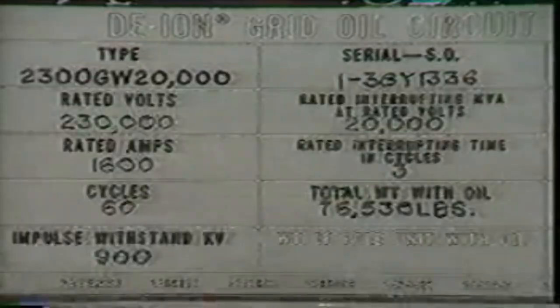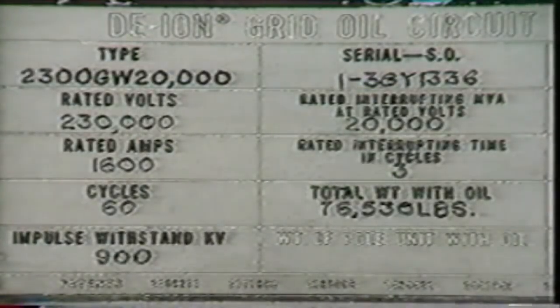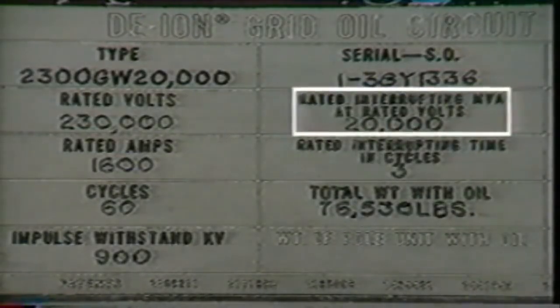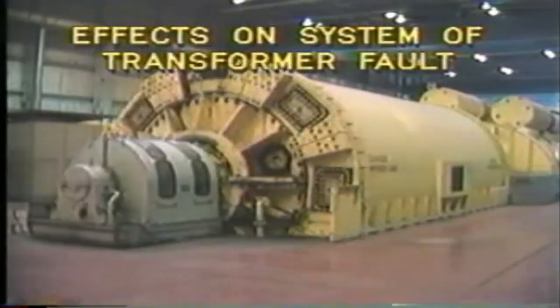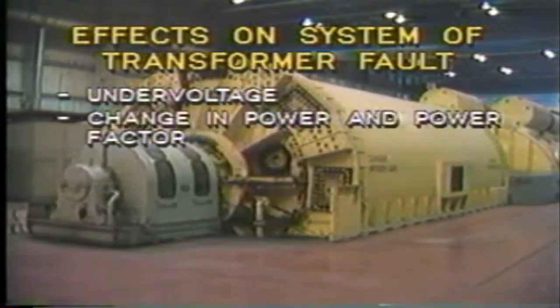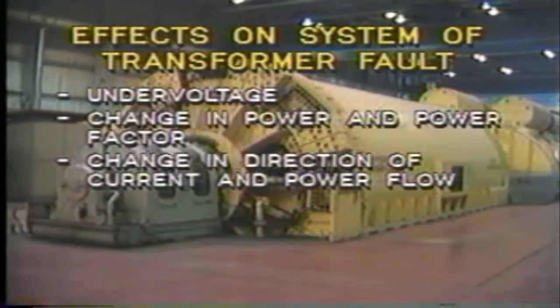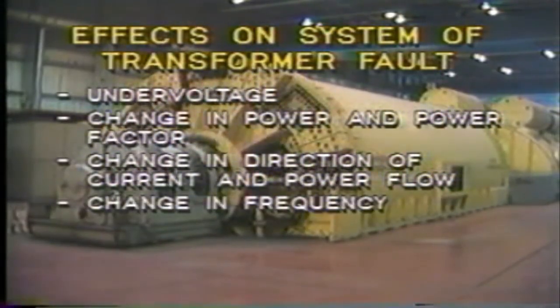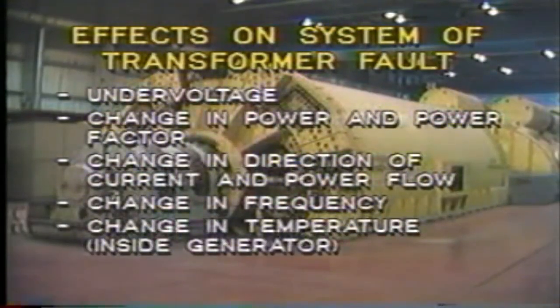Now, why is this? Well, any switchgear which is installed must be capable of handling the fault current. If a breaker is undersized, it could be completely destroyed when trying to clear a heavy fault current. However, as you know, overcurrent is not the only effect resulting from fault conditions.